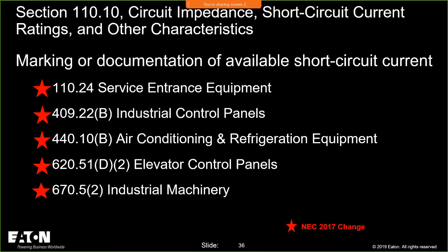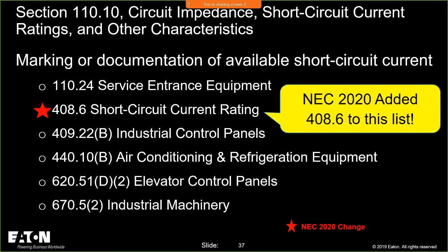And then the stuff that's in 409, 440, 620, and 670 is all new for the 17 code cycle, where you either have a field marking or a documentation of available short circuit current or available fault current for each of those equipment. And that cannot be put on in the factory. That's all going to be field marked because, for obvious reasons, short circuit current is dependent upon the impedance of the system within which it's installed.